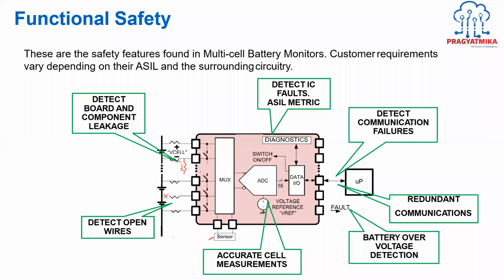These are the tests that will be done in the design: detection of current leakage, open wire conditions, cell measurements and how much accuracy you have, whether your battery pack's overvoltage is detected or not, communication redundancy, and if communication fails, whether that gets detected or not. All these are the functional safety standards expected from your battery pack's BMS front-end chip.